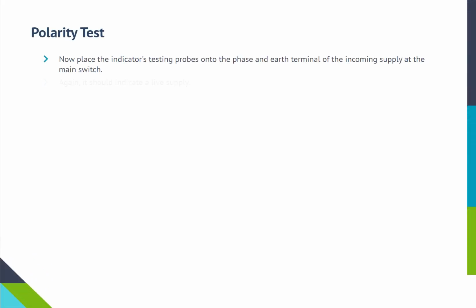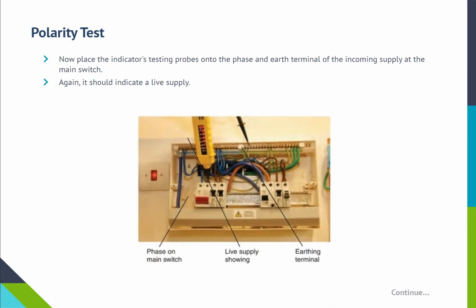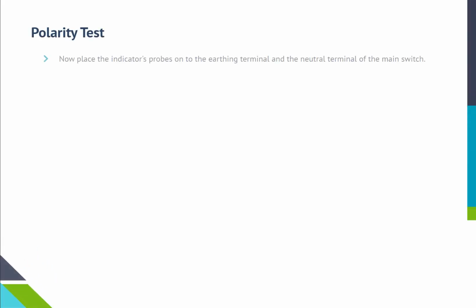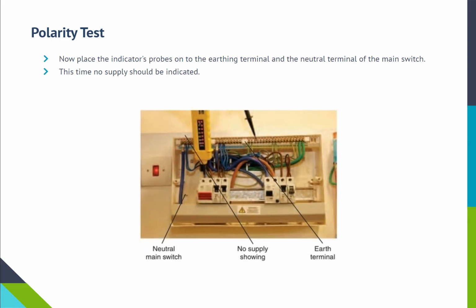Now place the indicator's testing probes onto the phase and earth terminal of the incoming supply at the main switch. Again, it should indicate a live supply. Now place the indicator's probes onto the earthing terminal and the neutral terminal of the main switch. This time no supply should be indicated.